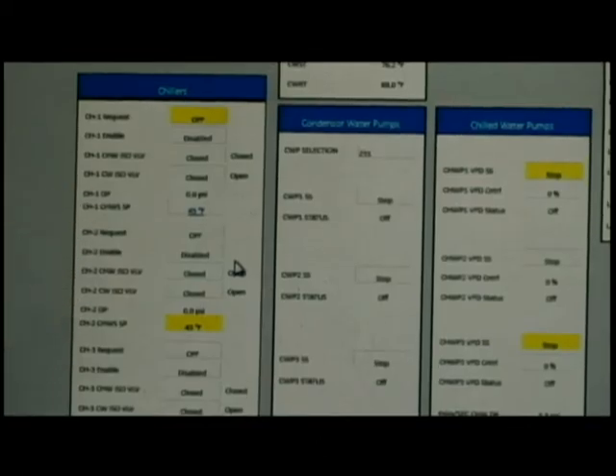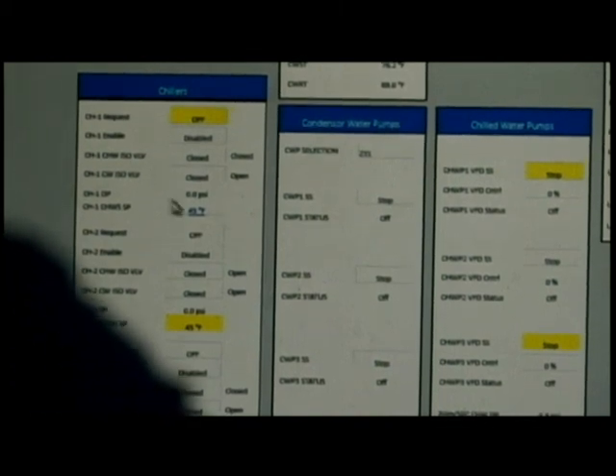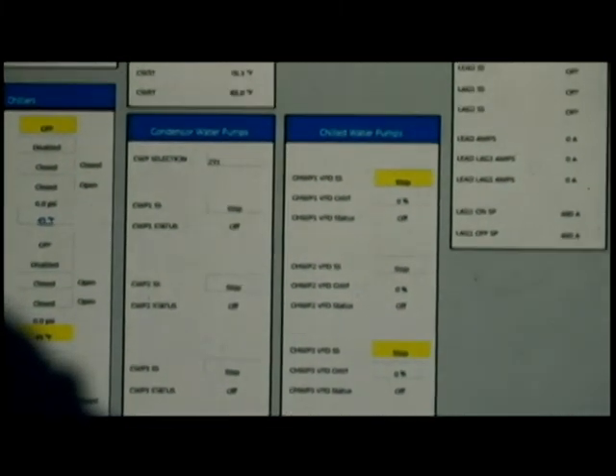So if there were a case where the chilled water set point resets throughout the day, we need to make sure that these chilled water set points are in auto so that programming can dictate what that set point should be throughout the day. Put this back to the state it was.